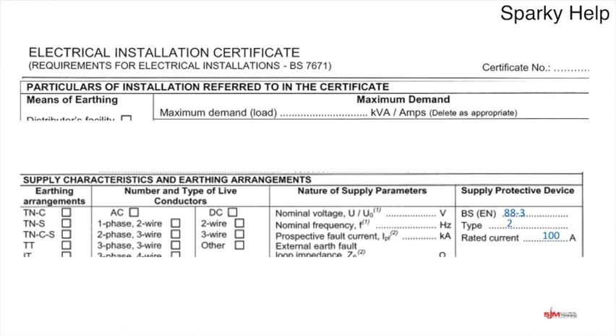What maximum demand is not is the 100 amps of the incoming fuse. This is a common misconception and error — people write the protective device size on the incoming supply as the maximum demand. That's not what it's for. If it were, there would be no need for maximum demand at all; we'd just use the protective device.